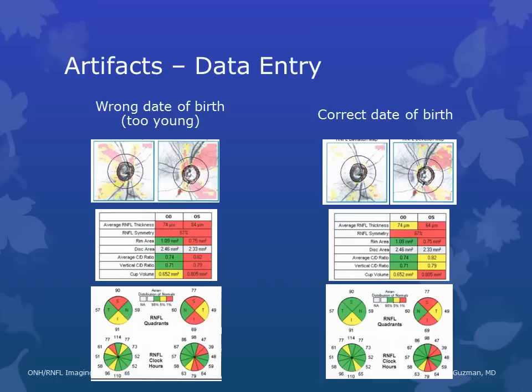Just like with visual field tests, accuracy of data entry is important. Date of birth matters because the patient is compared to an age-matched normative database — if you input the wrong date of birth, the patient is compared with normals who are either too young or too old. In this example, the patient was compared with normals who were too young, and when the date of birth was corrected, the results did not appear as abnormal as they did when compared with much younger people.